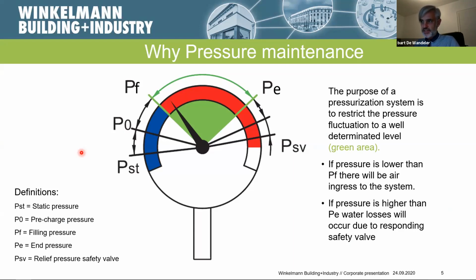A pressurization unit, or let's start with the static vessel, has a very important role in the behavior of a system. And also after commissioning, the system has to run smoothly, not with the installer having to go back to the system every month or every week to look at what is happening or to see what the problems are. So I will start a little bit with the pressure maintenance.